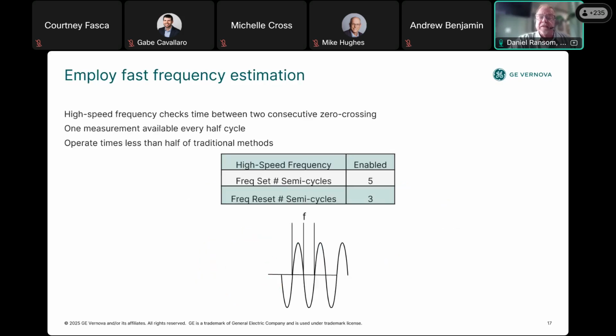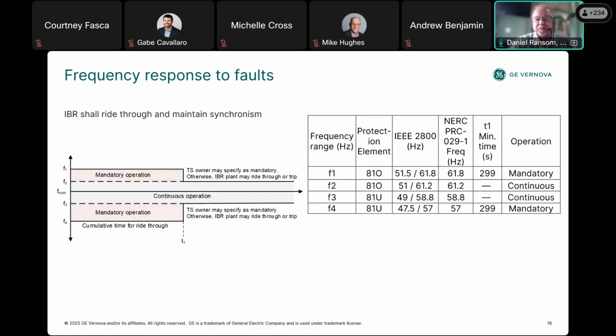So what we need to get a relay to signal the IBR plant controller is fast frequency response. The relays typically in the past used a whole cycle to measure frequency, and that was slower. So now we've got relays measuring half cycle crossings of the voltage waveform as seen here. So in this case then, as you can see in the slide, there are 5 to develop the count and 3 to reset the count. And in this way, we can get the times in half. And that's very, very important when you're trying to get grid stability going. Time is your friend.